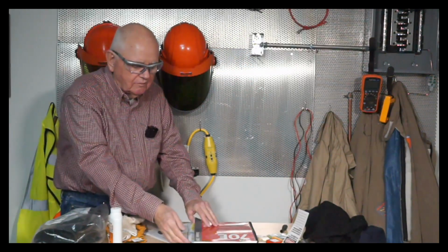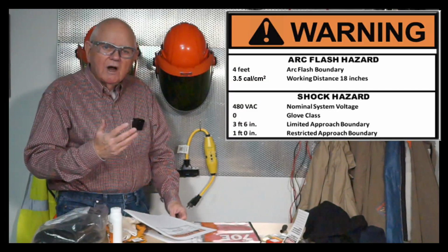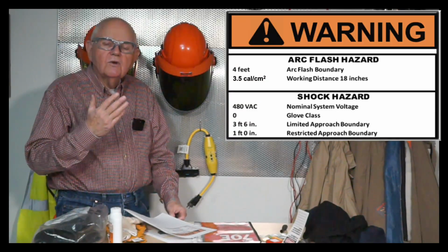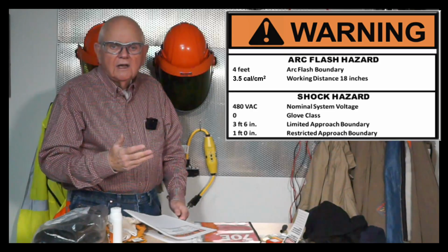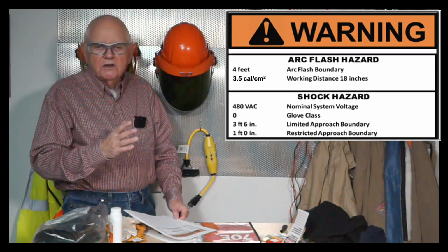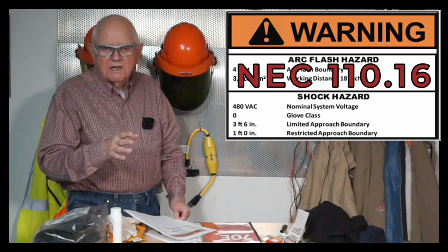So let's take a look at a label and see what the minimum requirements are. Now, there are different types of labels out there. Most facilities have labels that are specific to them, so whatever you have. But let's put up on the screen a typical label and see what the minimum requirements are. It's required by the National Electrical Code that I have an arc flash warning label on equipment. That's covered in 110.16.